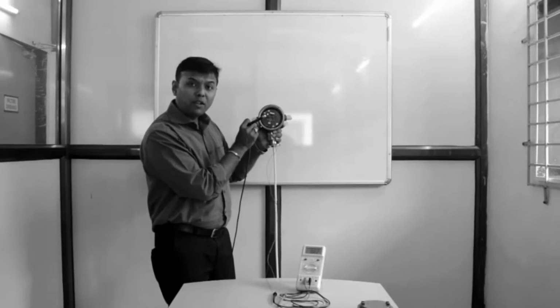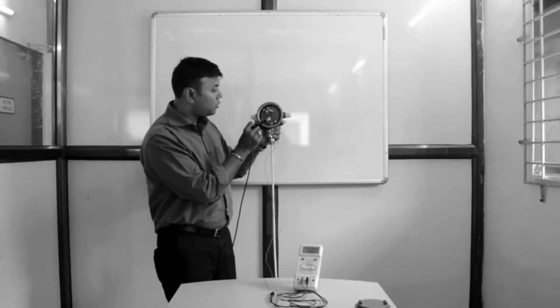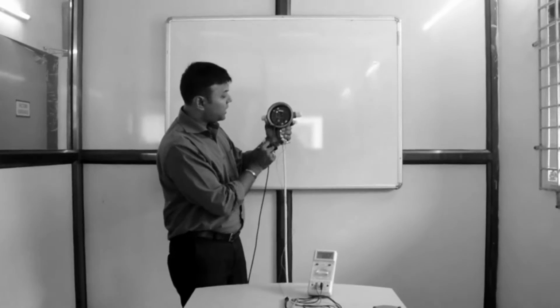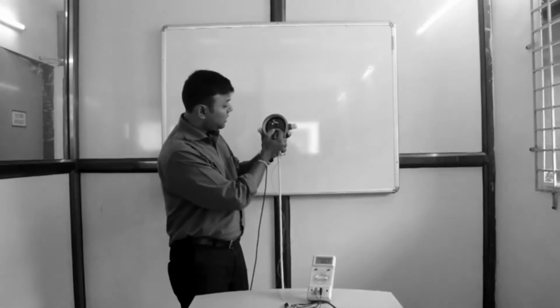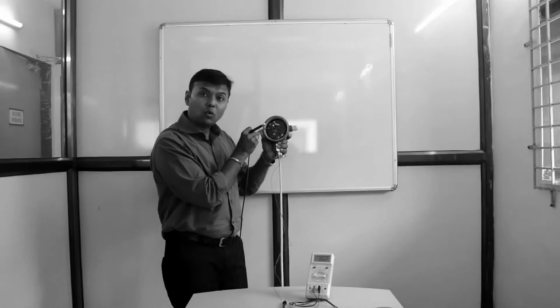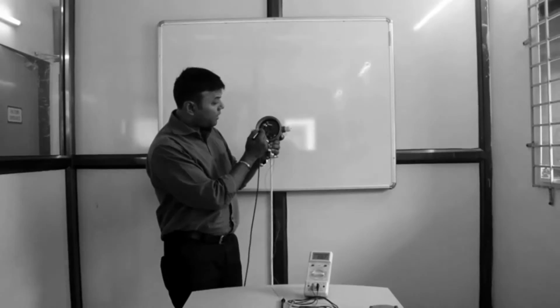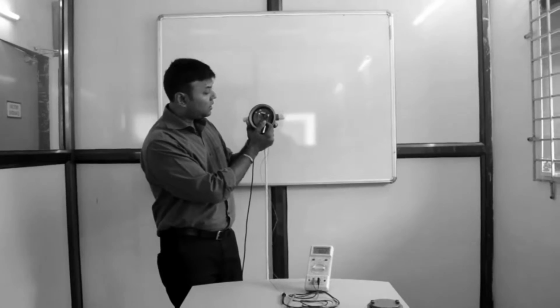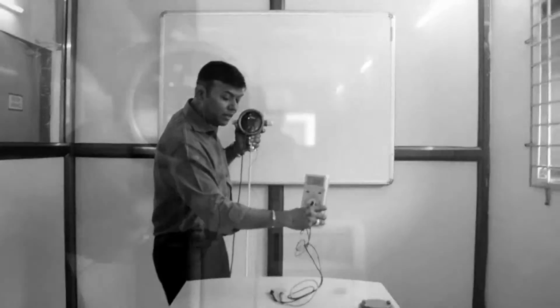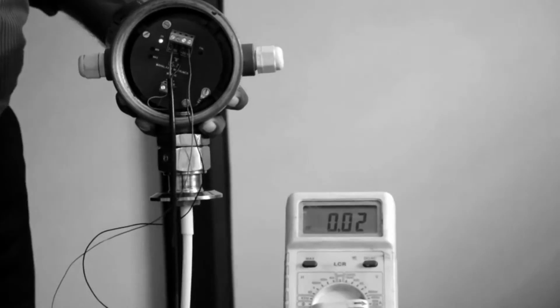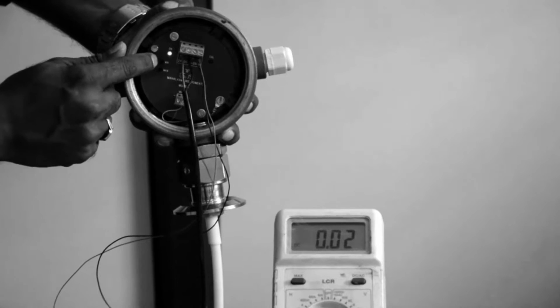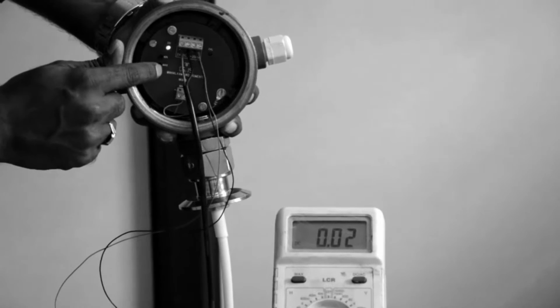This wire is the 24 volts DC power supply to the transmitter. The first terminal has been given 24 volts plus. The second terminal has been given 24 volts minus. And the balance 2 terminals we have connected to a multimeter. Okay, we are going to start with the current calibration now. You can see that there are 2 push buttons, minimum and maximum.